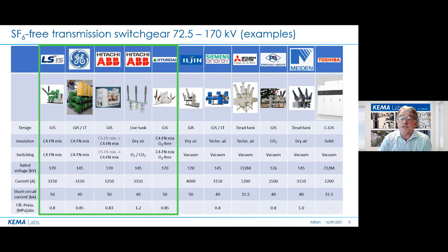A number of different mixtures are still applied, depending on manufacturers, but also within a single manufacturer we see different mixture compositions. Note that there is also a product, a live tank breaker, which uses only CO2 and O2 for insulation and breaking. Future CO2, O2 GIS products are announced. The absence of F-gas enables, in this case, a very low temperature application, but also needs higher pressure to cope with the dielectric requirements.